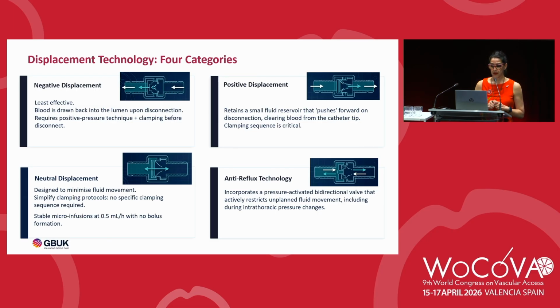The positive displacement retains a small amount of fluid inside the reservoir that is pushed forward on disconnection, but again, clamping is recommended for this kind of needle-free connector. On the other hand, neutral displacement needle-free connectors are designed to minimize fluid movement and to simplify the whole maneuver. And for these and the anti-reflux technology needle-free connectors, clamping is not needed.